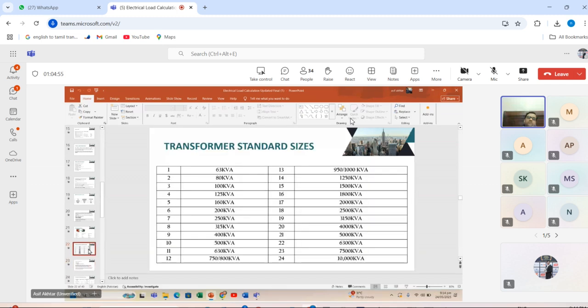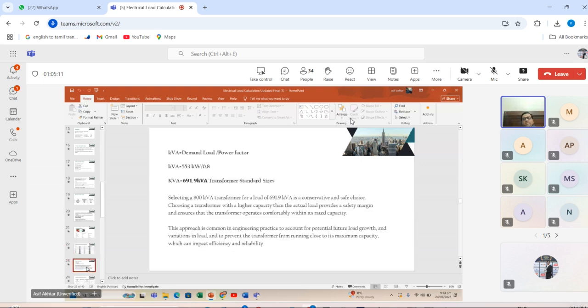There is no transformer between 630 kVA and the next higher rating of 800 kVA. So we will select the 800 kVA transformer for this high-rise building. Selecting an 800 kVA transformer for a load of 691 kVA is a conservative and safe choice. Choosing a transformer with higher capacity than the actual load provides a safety margin and ensures that the transformer operates comfortably within its rated capacity. This approach is common in engineering practice to account for potential future load growth and variation in loads, and to prevent the transformer from running close to its maximum capacity, which can impact efficiency and reliability. I hope this point is clear now.